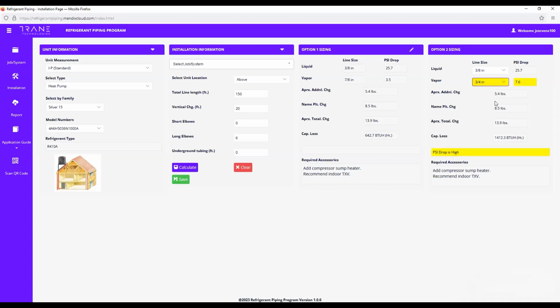Let's go to 3/4. Yellow again. This is for if you absolutely had to use it this way. Okay. I wouldn't use it just because we have a high pressure drop. You don't want high pressure drop. You can cause problems. Okay. So we're going to select 7/8 and it goes to all white. When it's all white, that's good. Okay. So you know that you could use this.